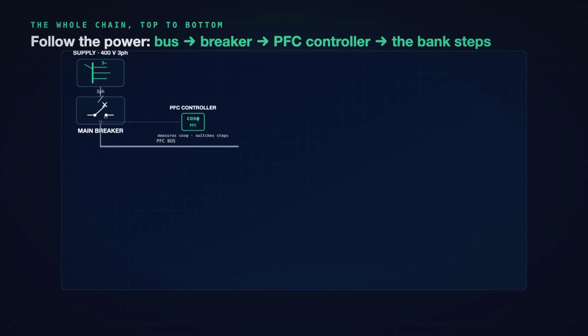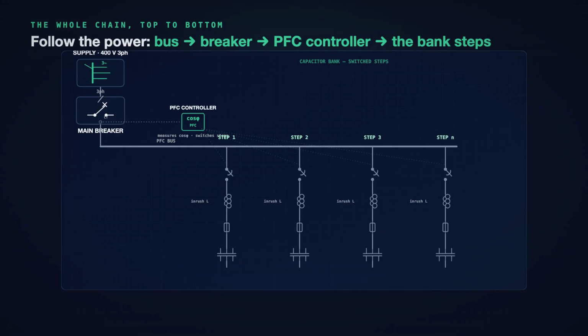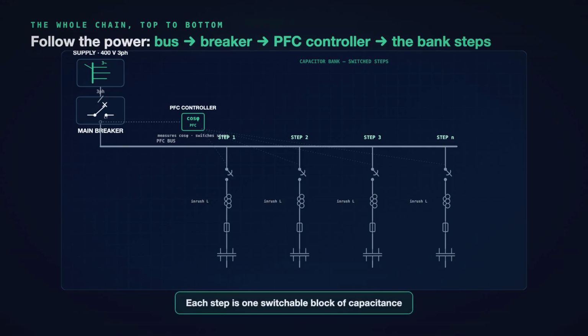Here is the whole chain, the way this drawing reads. Top down into the bus, then the steps hanging off it. The feed comes in from a supply, three-phase, at your panel voltage. It runs through a main breaker or a fuse switch for short circuit protection. That lands on a bus, the bar the whole bank hangs from. Watching that bus is the PFC controller, the brain measuring the power factor. And dropping off the bus are the capacitor steps, each one a switchable block of correction. Learn that shape, bus, breaker, controller, steps, and the whole diagram opens up. Let's take it one block at a time.